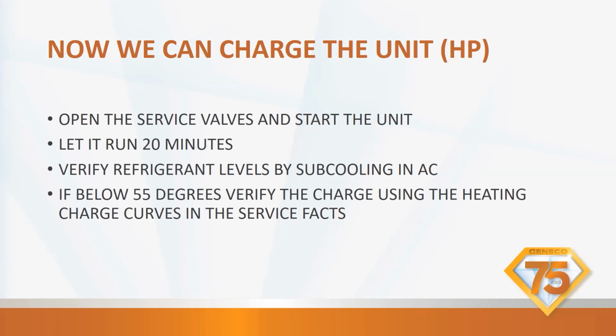You still need to come back in the summer when it's above 55 degrees outside, and preferably above 70, because you can really get a right-on charge that way. And then re-verify your charge when it's warmer outside.